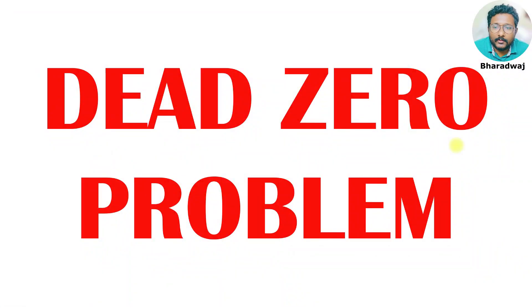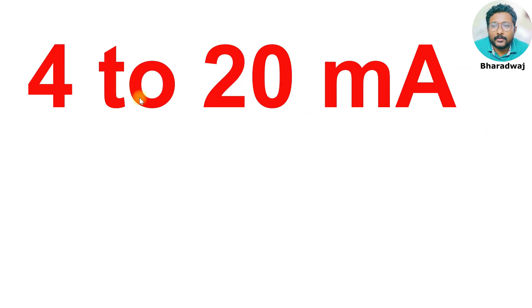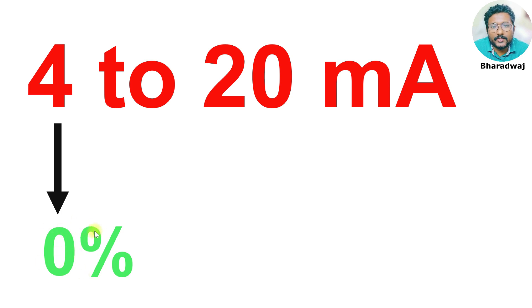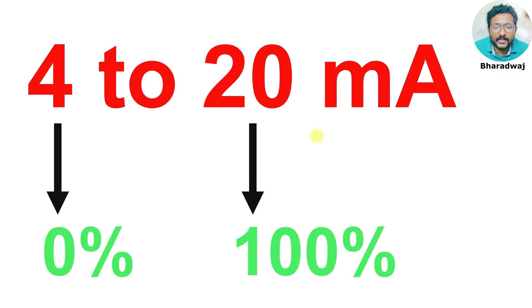In this video I will discuss the dead zero problem. In the previous videos, we discussed about 4 to 20 mA. The 4 represents the zero scale reading or 0% of the process variable, and the 20 represents the full scale value, which is 100% of the process variable.